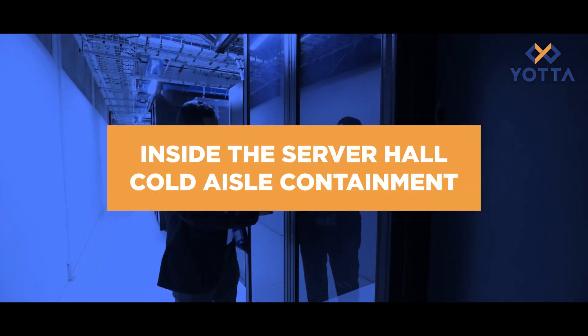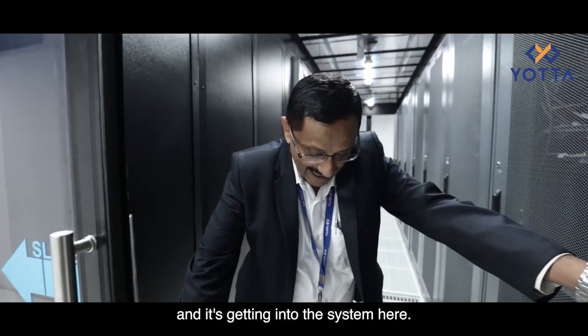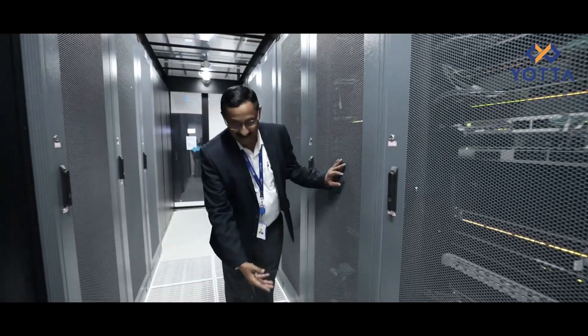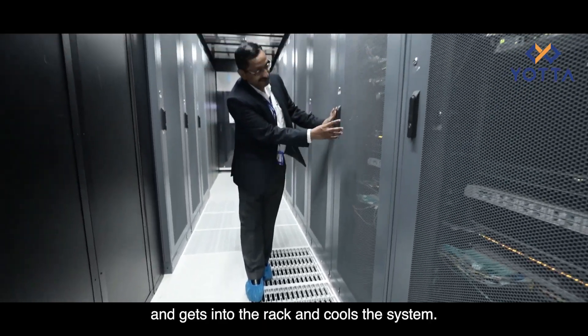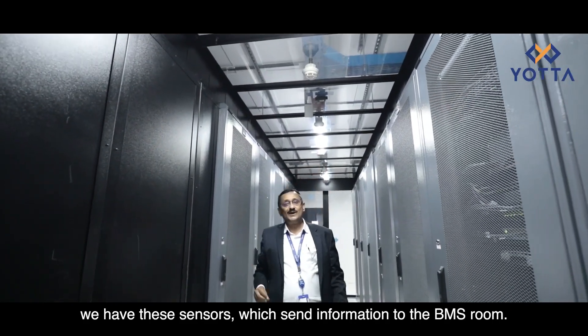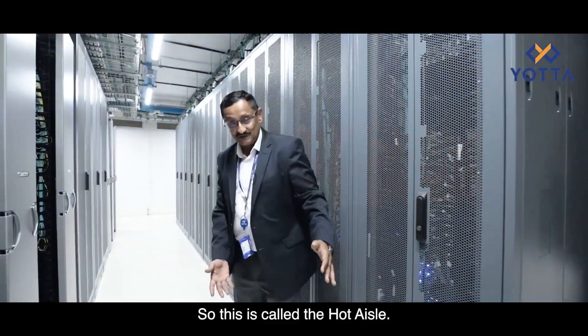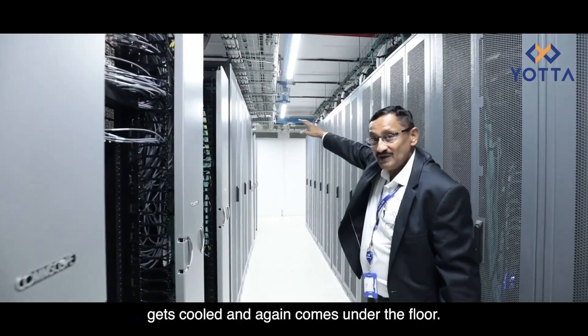These are containment units where cold air comes from under the floor and gets into the system. These are racks which contain our equipment, and wherever we require cold air we replace the normal tile with a perforated tile so air comes up and cools the rack. This is called cold air containment. On top of the racks we have sensors which send information to the BMS room. The hot air comes out from behind the racks — this is called the hot aisle — and that air is pulled in by the PAHU machine fans, cooled, and sent back under the floor.